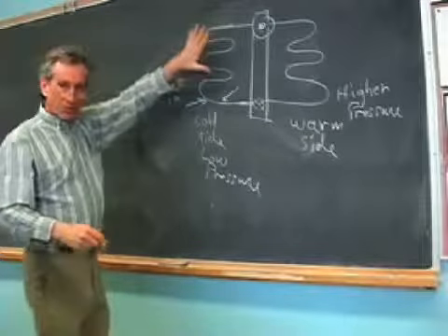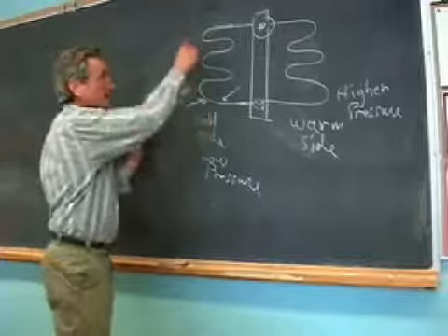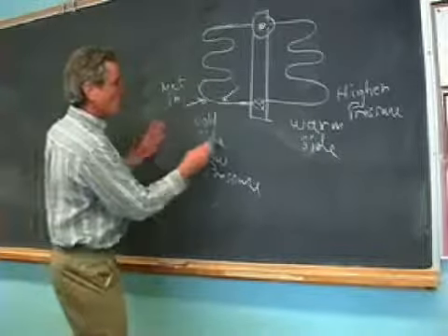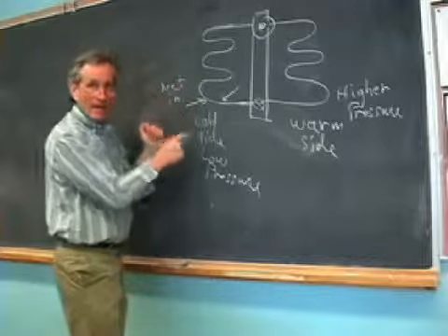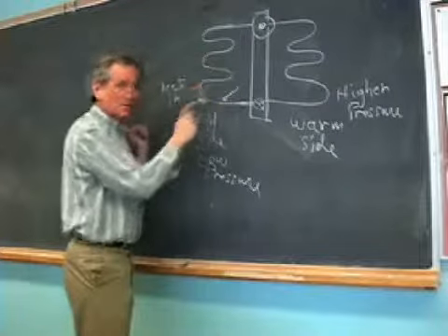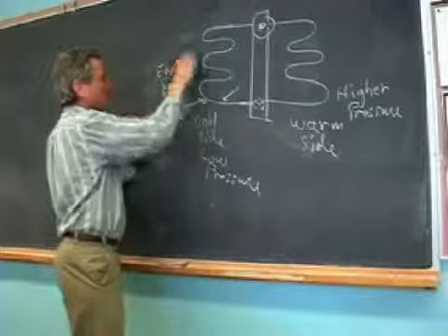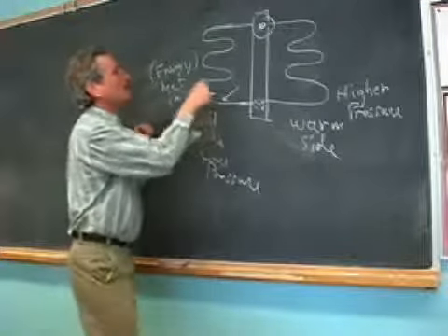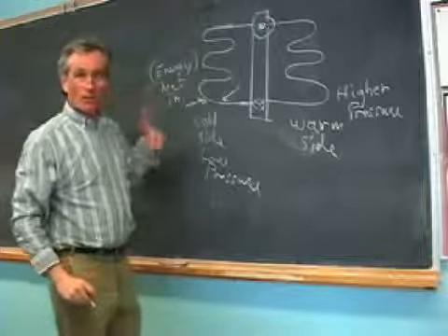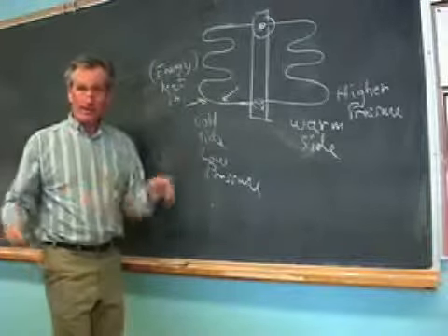Now, in the heat pump system in the Education Center, these coils are in a heat exchanger where the water from the ground is going through. So what that means is the water, as it passes through this heat exchanger, is giving up heat, energy, to the coils here. So energy is actually going in. In other words, heat is energy. Okay, energy is going in. And that means the water that passes through this heat exchanger comes out colder than when it went in. So that means it has given up energy. And that's the free energy that we get from the ground. That's the geothermal energy.